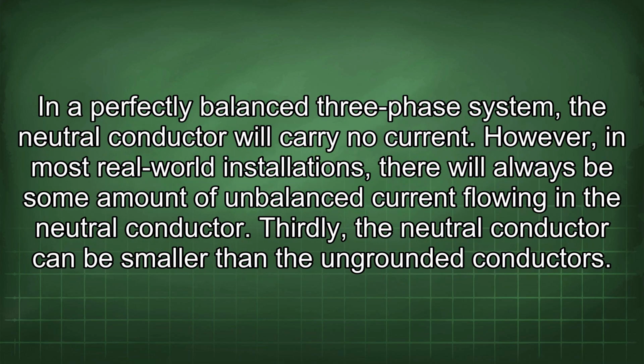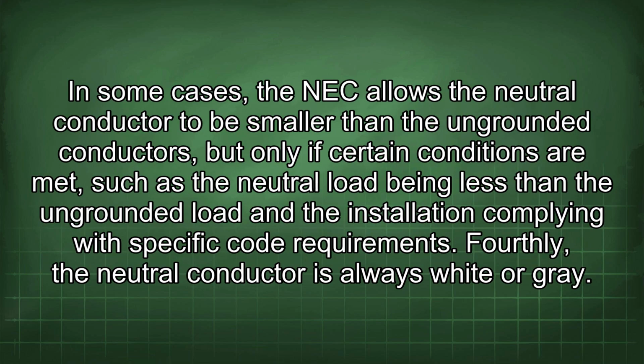In a perfectly balanced three-phase system, the neutral conductor will carry no current. However, in most real-world installations, there will always be some amount of unbalanced current flowing in the neutral conductor. Thirdly, the neutral conductor can be smaller than the ungrounded conductors.